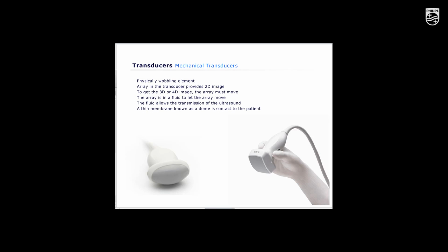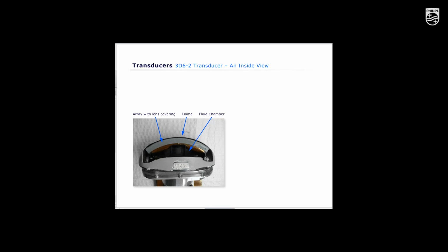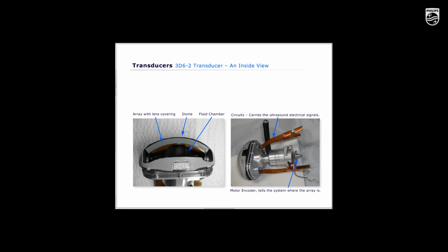Mechanical transducers are linear or curved transducers. The array stack and lens can be moved by using a motor inside the transducer to move it back and forth. Here you can see the inside of a mechanical 3D probe. Here is the array, dome, and fluid chamber of a Philips 3D6-2 3D probe. This is a 3D6-2 before the cable is attached and the housing is installed, showing, among other components, the motor.